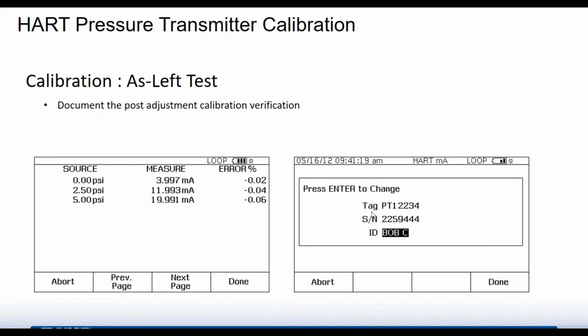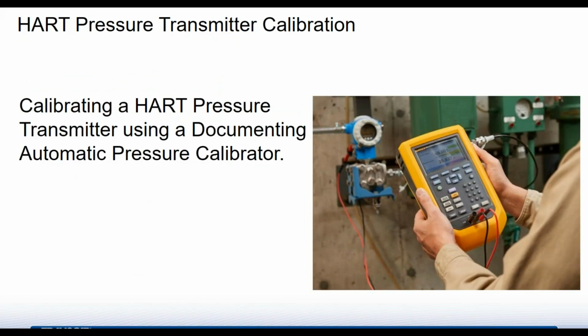You would then, again, document those test results, so that you've got your as found and your as left results. Now you've finished your calibration. This information is documented and saved in the calibrator, and we'll talk about what we're going to do with that with the software in a few steps. Okay, so that's how you do it with a hand pump.